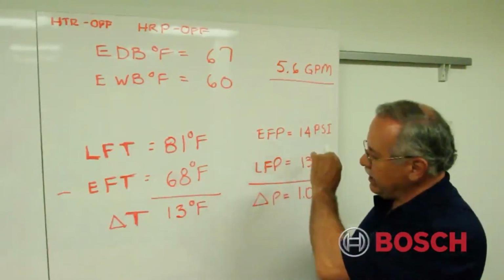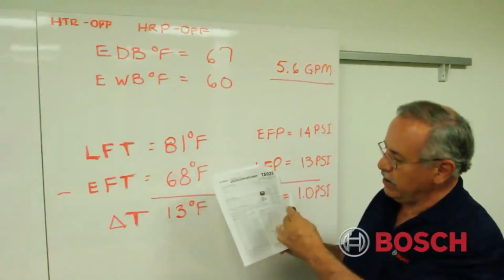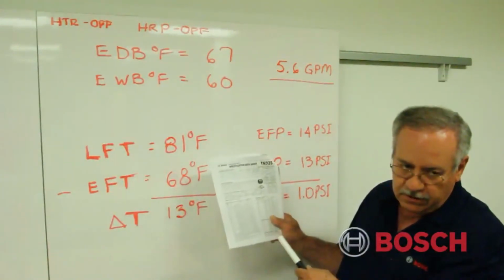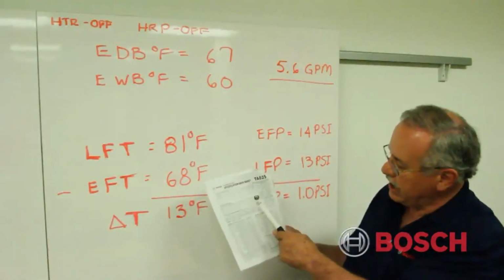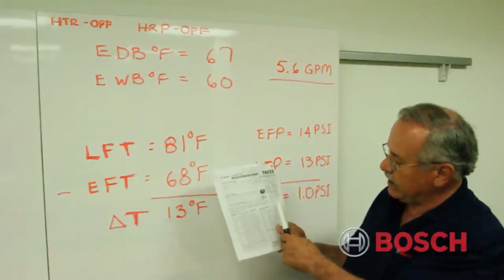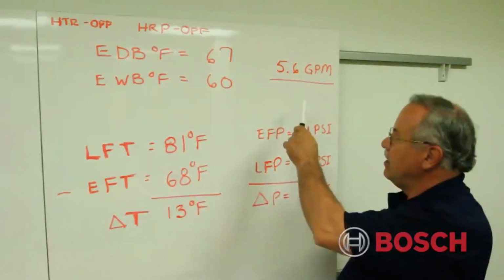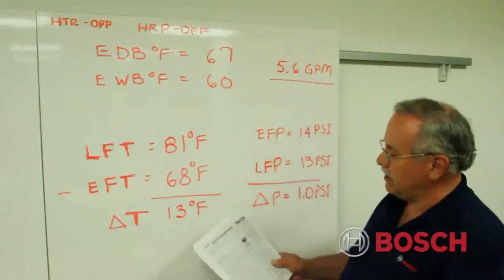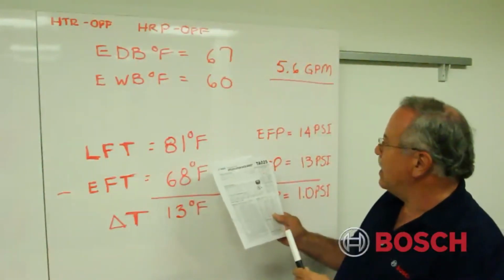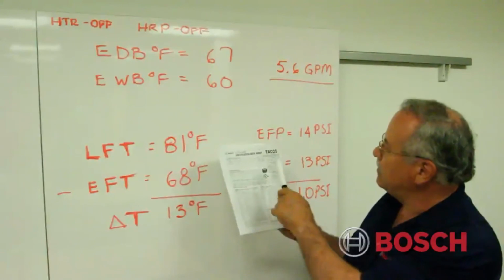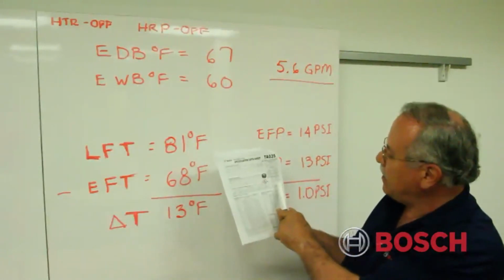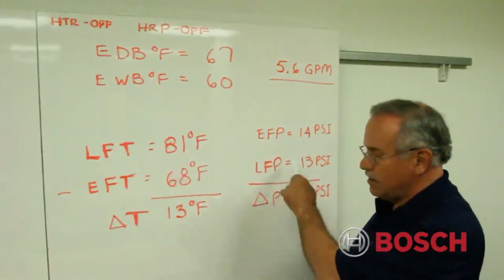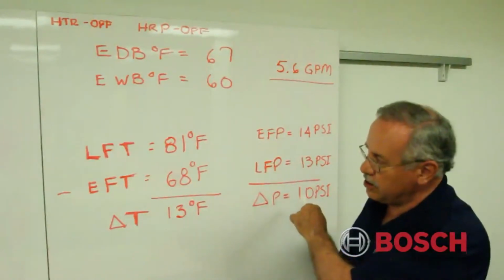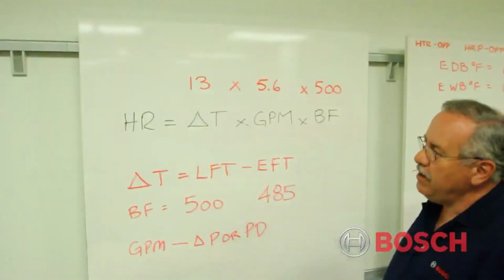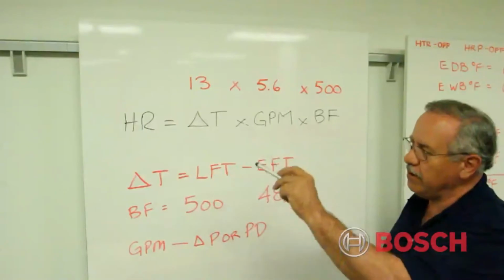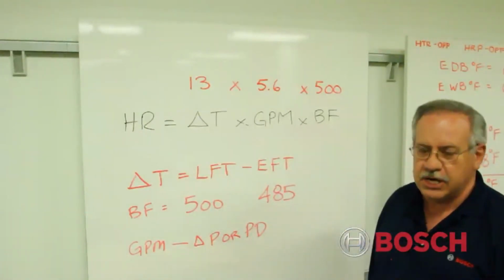So we take this information and we go to the current TA025 full load data. On the middle of the right side of the page, you're going to find in the spec data fluid pressure drop. What appears closest in our data is 5.6 GPM at approximately 1 pound of pressure drop.